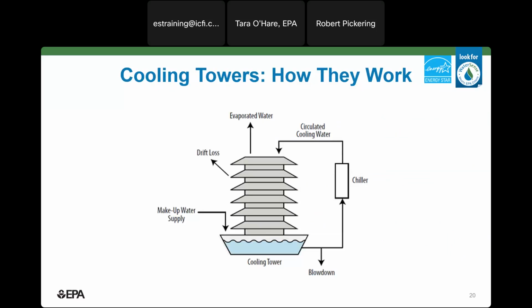So that we have everyone oriented on cooling towers, I just want to take a moment to go over some of the basics. The concept is fairly simple. Water and air flow past each other, typically in a countercurrent or cross-flow configuration. In this schematic illustration, hot water from the chiller is introduced at the top of the tower by spray nozzles and flows down along a fill material while air is drawn up through the tower by a fan. As the air passes over the water, some water is evaporated, which removes heat and reduces the temperature of the water in the tower. The energy lost via water evaporation helps remove heat from the system, and then this cooled water is returned to the chiller to collect more heat.